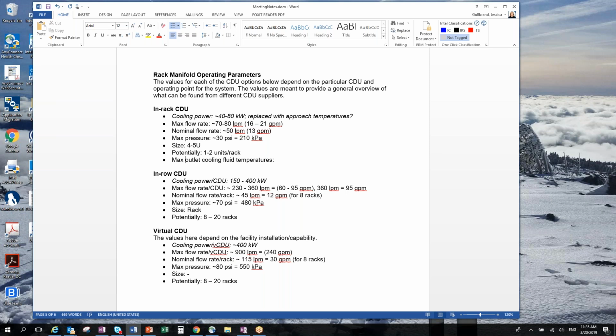One comment, and I don't know if there's a right or wrong way to do this, but when I think about the manifold, I think about it the other way. The manifold is sized to meet the capacity of the IT equipment. So you kind of have to start with the IT equipment cooling demand, and the CDUs on the other side just need to meet that demand. The manifold needs to be designed to support the flow rate requirements of the IT equipment.